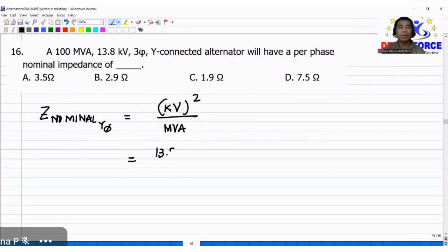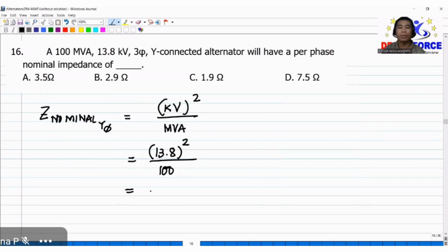Kilovolt 13.8 squared divided by MVA, that is 100. So the nominal impedance per phase connected in Y is equivalent to 13.8 squared divided by 100. So that will be 1.9044 ohms. So letter C.